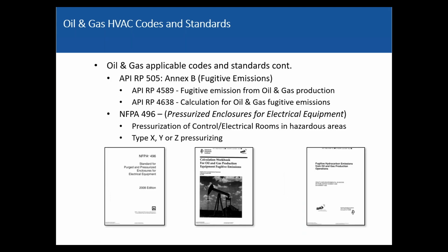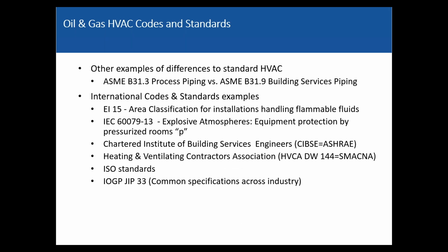All right, more codes. API RP 505 Annex B talks about fugitive emissions. So these are 4589, 4638. Those are two good guides for how to calculate the fugitive emissions. NFPA 496, that's the big one that if you're doing HVAC, oil and gas, you're going to worry about. That's the pressurized enclosures for electrical equipment. Pressurization of control rooms, electrical rooms. Yeah, Type X, Y, and Z pressurization. That's a big one. Okay. Other examples where codes and standards are different.